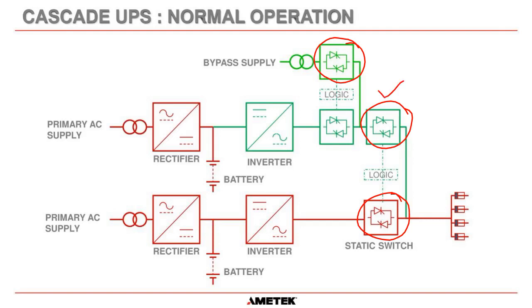So this static switch could be a single point of failure if UPS B is supplying the load and it fails, and the bypass needs to supply power through this static switch. If that has failed, then you will lose power to the circuits. So that is the downfall of a cascade system.